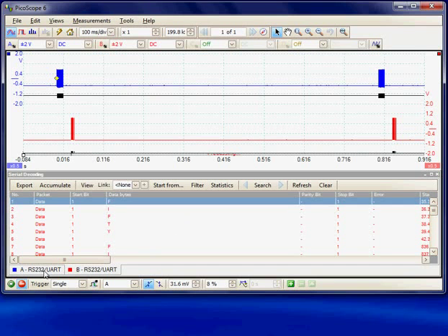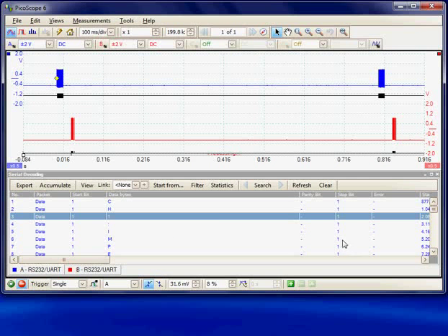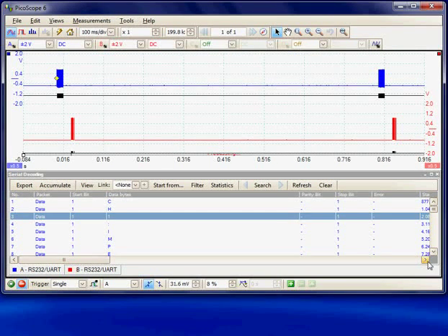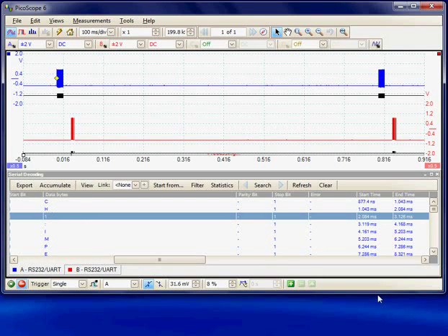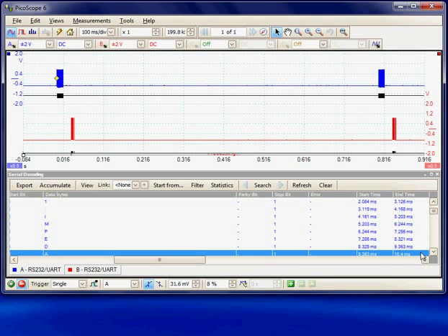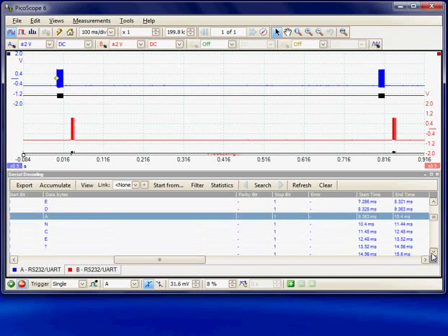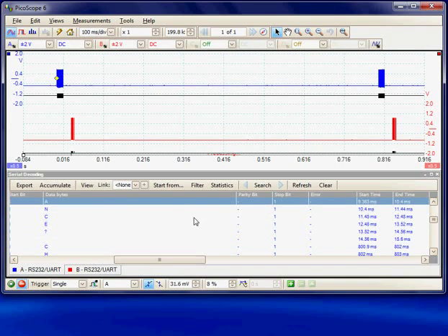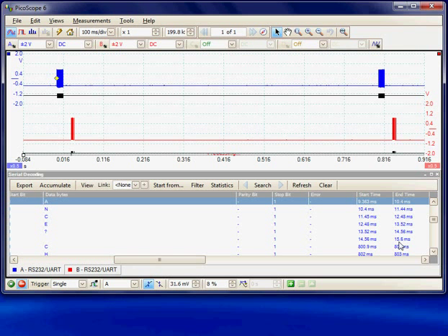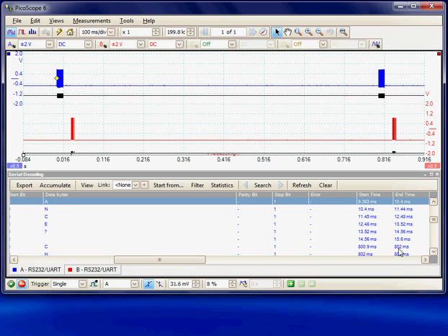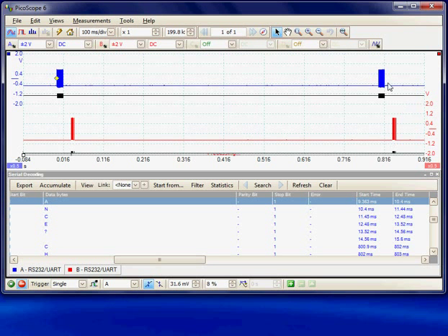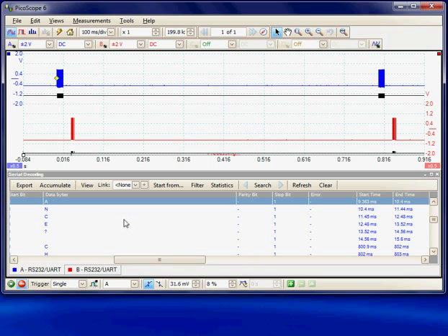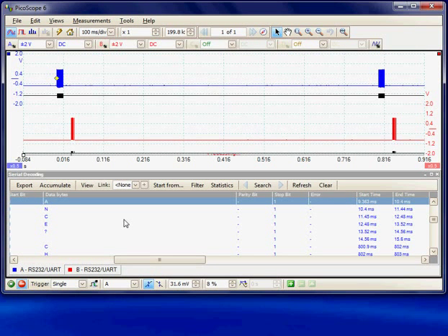We could see the similar information here because we can see the packet time. Here we can see the first command going out, channel 1 impedance query. The last bit of that went out in 15 milliseconds, and then some 802 milliseconds later the second transmission occurred. We can use the decoded data to do any time calculations on transmissions.